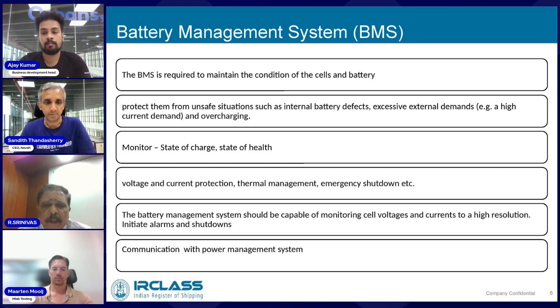The battery management system should be able to monitor voltage and currents at high resolution, and it must always communicate. It has to be integrated with the wider power system, because apart from the batteries, if you're operating in hybrid mode, there could be other generators and the main switchboard powering up.